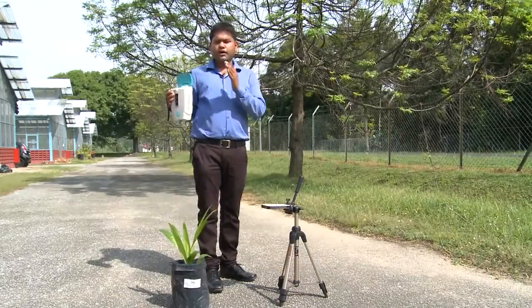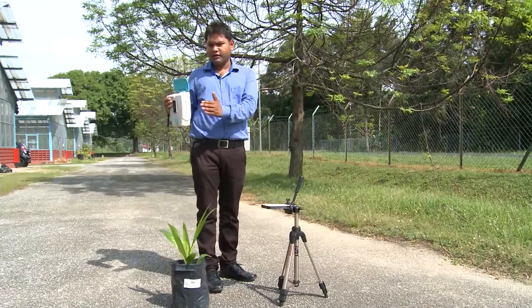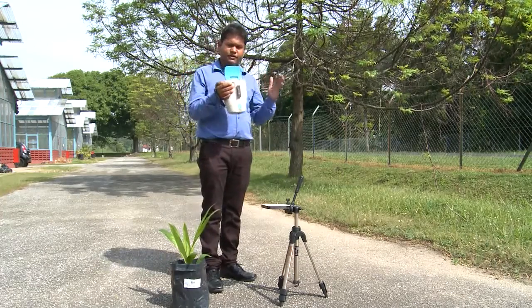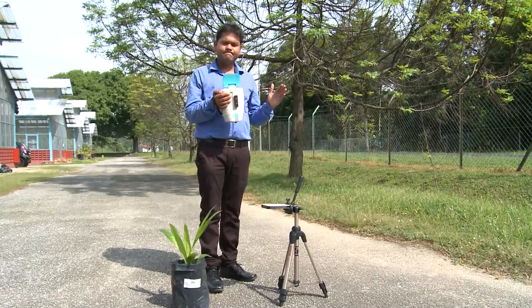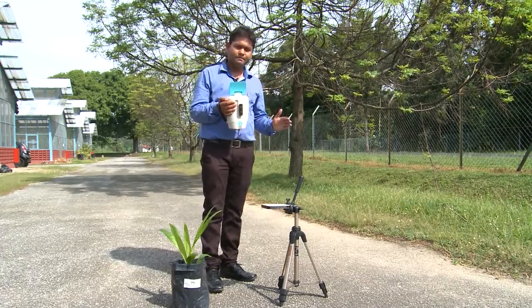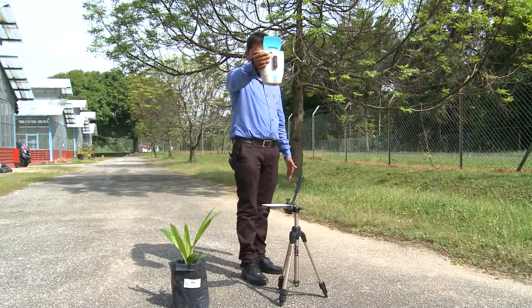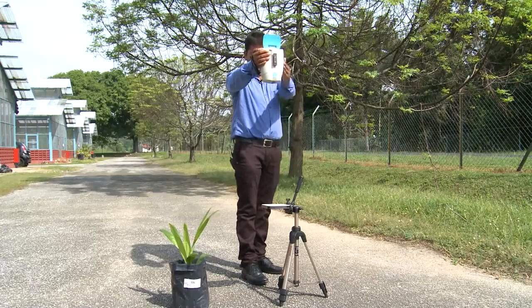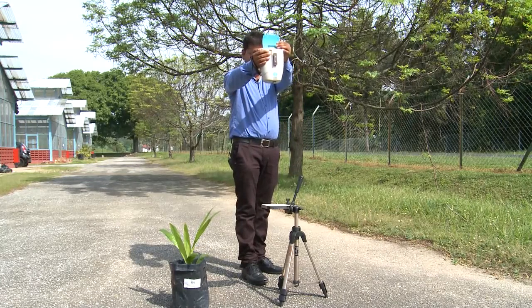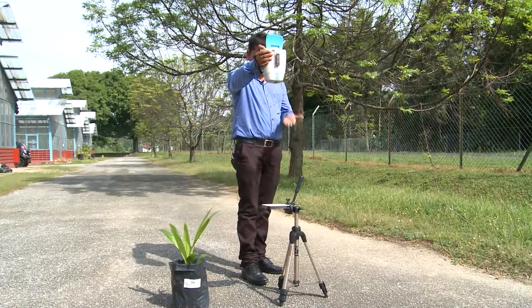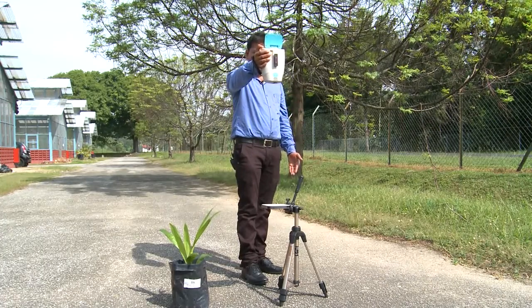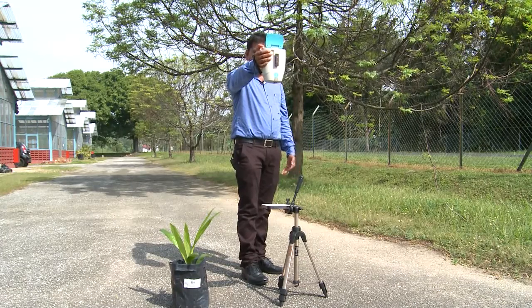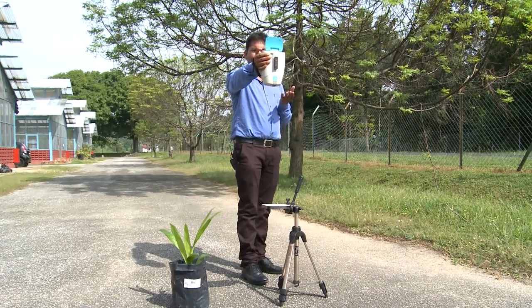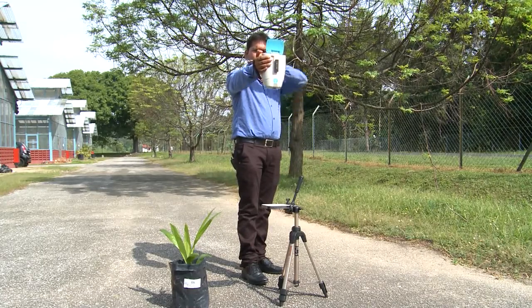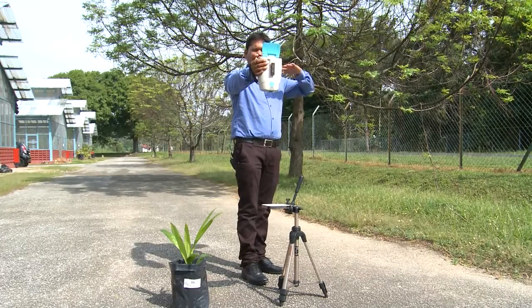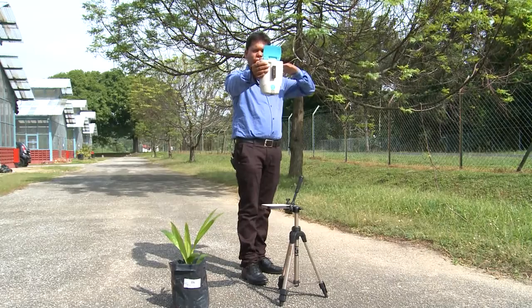In order to take reflectance from an inoculated plant, first I will take the reference from the white reference panel. I will mount the white reference panel and target my spectroradiometer to it. There is one laser point button. The distance should be around 50 to 80 centimeters, and I will press the trigger button. One beep sound comes, and after that one straight line comes. It shows that I have taken my reference successfully.